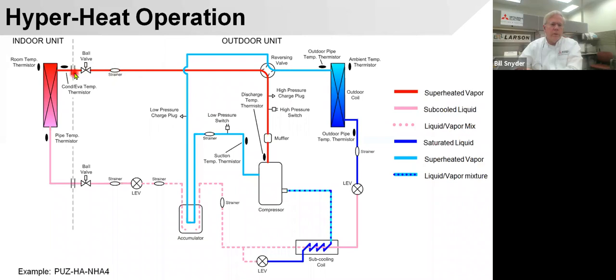So we go through, this is your line set to the indoor unit. You have an entering coil temp, condenser evaporator temperature, that's the entering coil temperature. We have a room temperature thermistor, that's a return air thermistor, measuring the return air temperature. And we have a leaving coil temperature. So we have the superheated vapor going through and getting cooled off through this condensing coil, which is now inside coil, heating the home. We leave there with subcooled liquid back through the service valve on the outdoor unit.